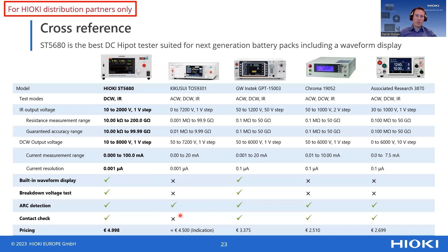So we see Kikusui rather as a competition because of this kind of resolution, but what Kikusui cannot do is, for instance, the waveform displays, but also the breakdown voltage test. This is especially important for the class type tests. What you have as a requirement for designing the battery pack or module, you also want to have later on with the safety test and offline test. So here with the ST5680, you have an all-in-one device, and also the contact check function, a very important feature for the automation industry.